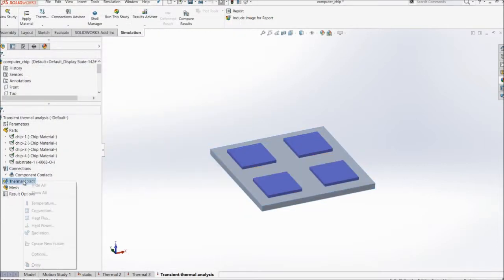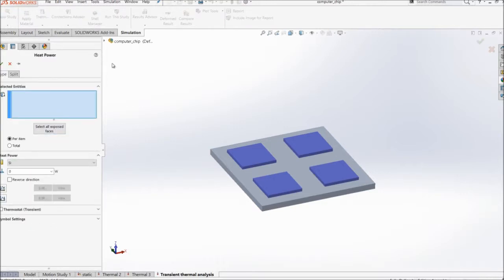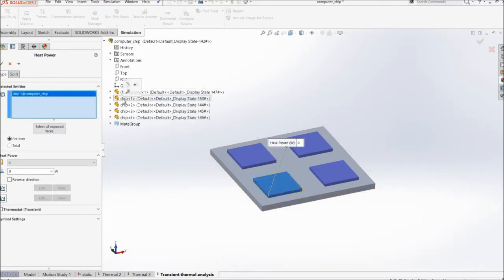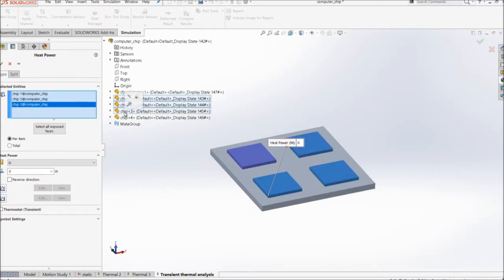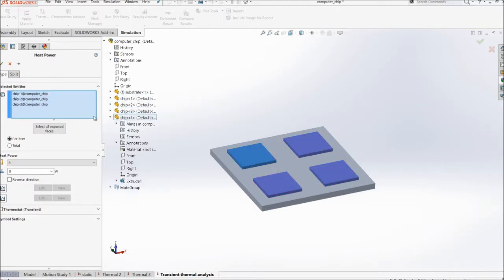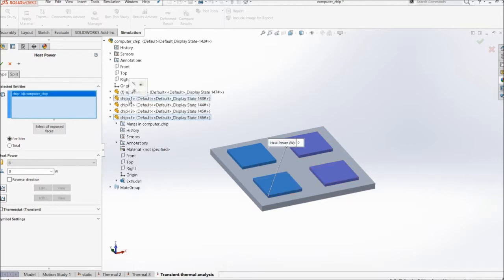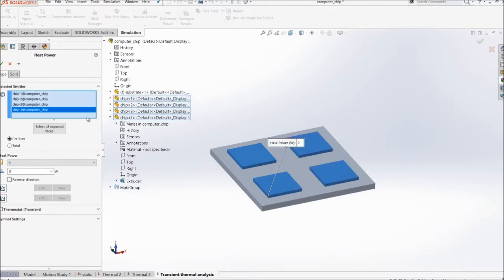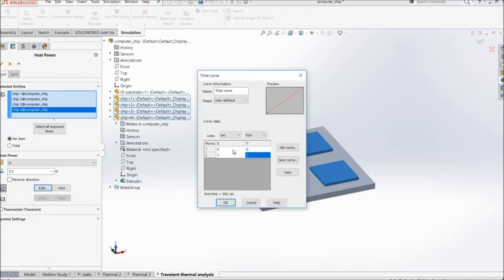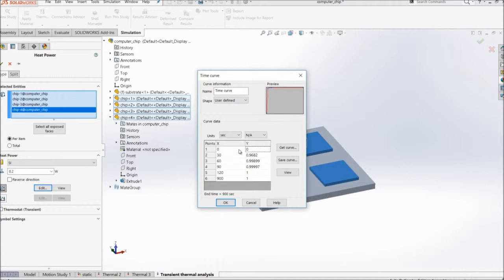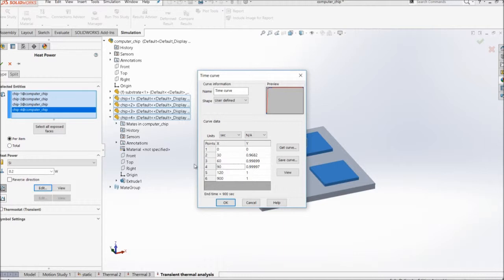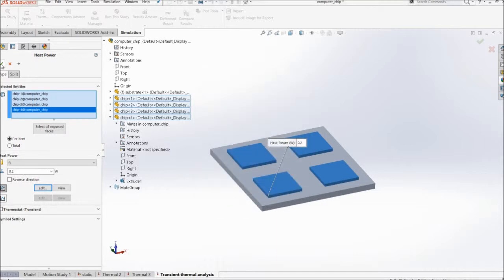So now I'll just select all the four different chips and I'll just give the values 0.2 watts. And now I'll just select the time curve. I'll just activate the time curve here, edit. And here I'll just provide the values. So here you just have to provide the input time curve with respect to 0 seconds 0 watt, 30 seconds it's 0.9682 multiplied by 0.2, as well as at 90 seconds it's 0.99997 into 0.2. And at 120 seconds it's 0.2, full 0.2 watts which will be applied. So I'll just click OK. OK.